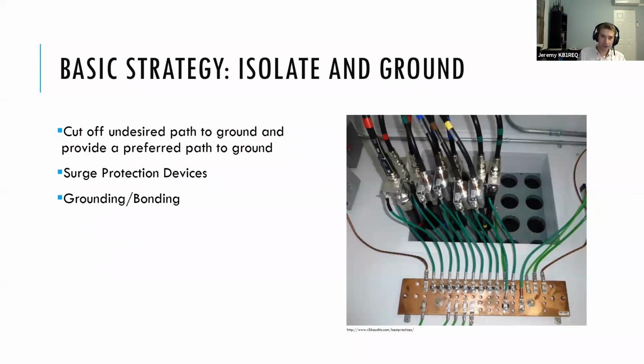So our basic strategy for dealing with electrical surges is to isolate them and then give them a path to ground. When we talk about our undesired paths, number one, we want to keep the lightning outside, and we're going to talk about the ways we do that in this entire section. And we also want to cut it off and give it a preferred route, a route that we design to ground, rather than letting it take whichever one it chooses, which is going to cause damage to equipment and also pose a hazard to us as the people working with this equipment.